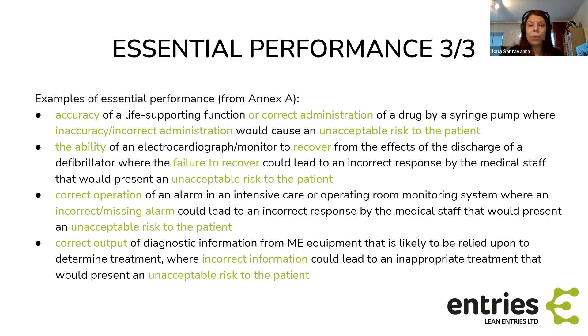Also correct output of diagnostic information from ME equipment that is likely to be relied upon to determine treatment. And again, incorrect information could lead to inappropriate treatment, and that could lead to unacceptable risk to the patient. And of course, the risk management file is in a very key role here to determine what is an unacceptable risk and what is not.